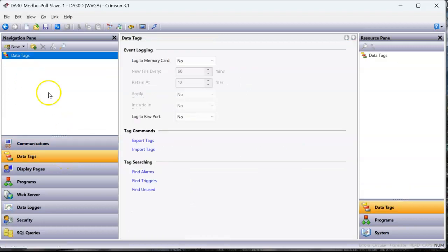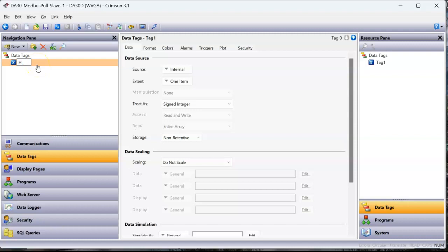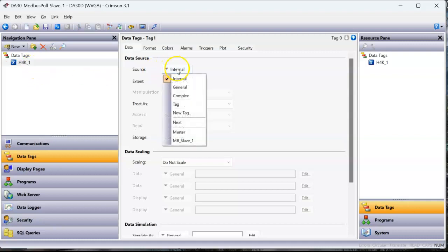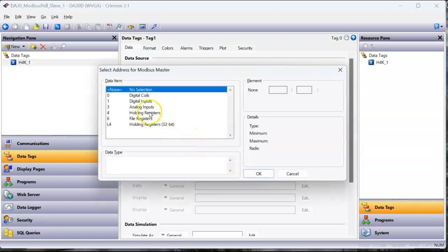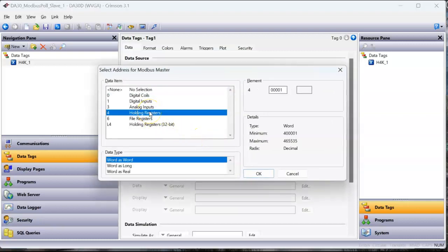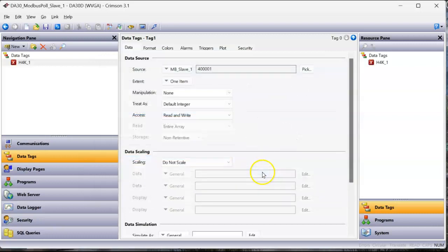Go over here to data tags. I'm going to create a new tag, new integer. I'm going to call this tag H4K for the 40,000 registers underscore number one, and that's going to be 40,001. So I'm going to hit the pull down here. I'll go down to that Modbus device. Click on it. Everything we're going to do is in the top holding registers, not the L4. Those are the Enron version. 40,000. Here's the first address. I'm going to leave it word as word because it's going to be integer for this test. I'll click OK, and that's about it.